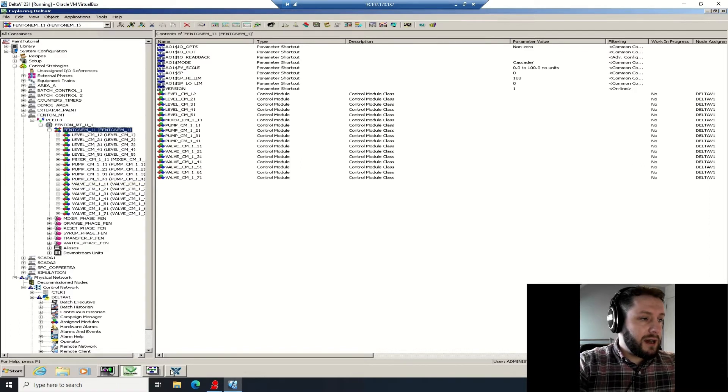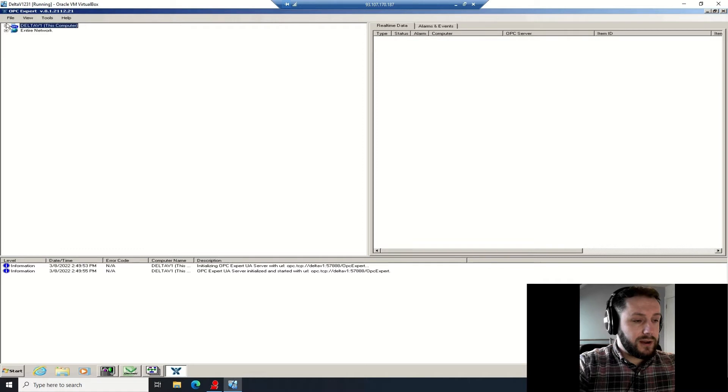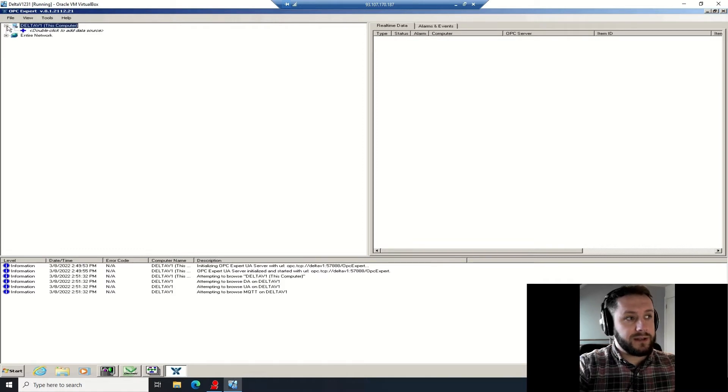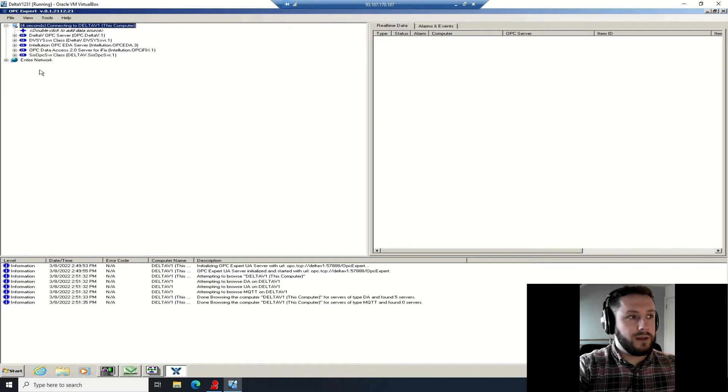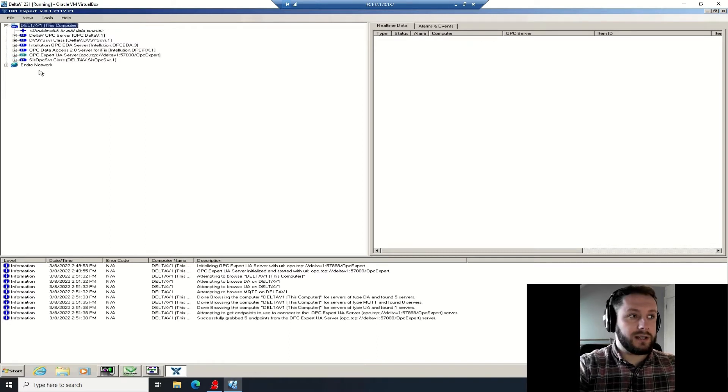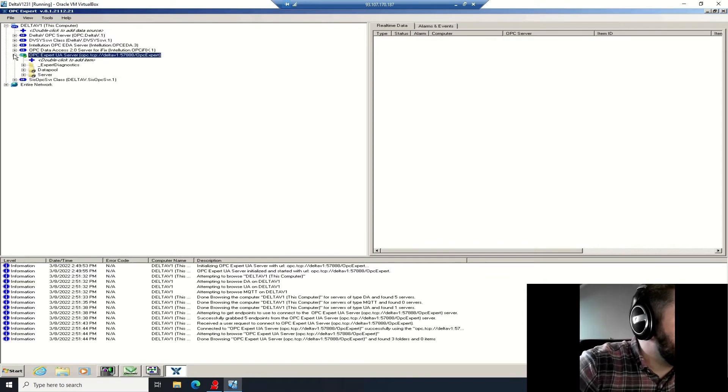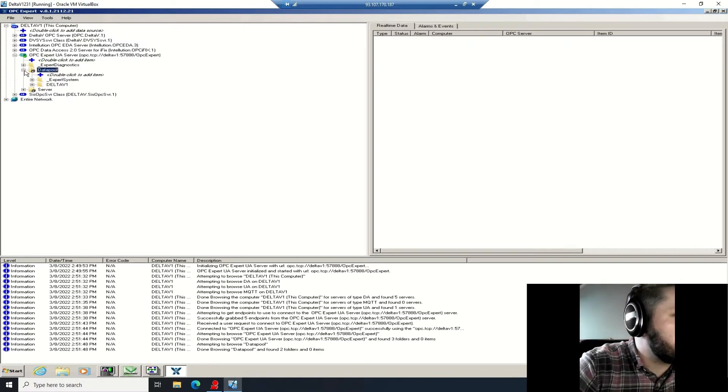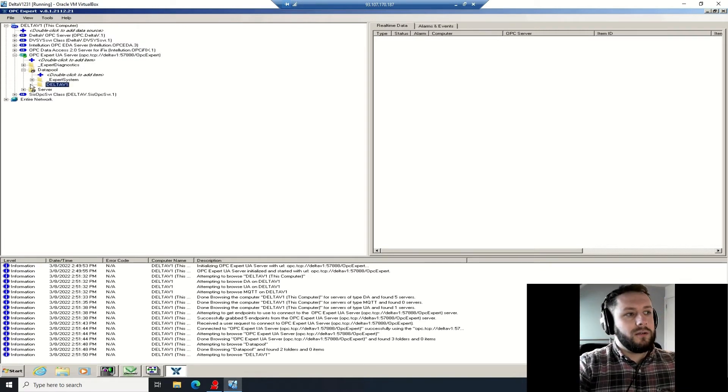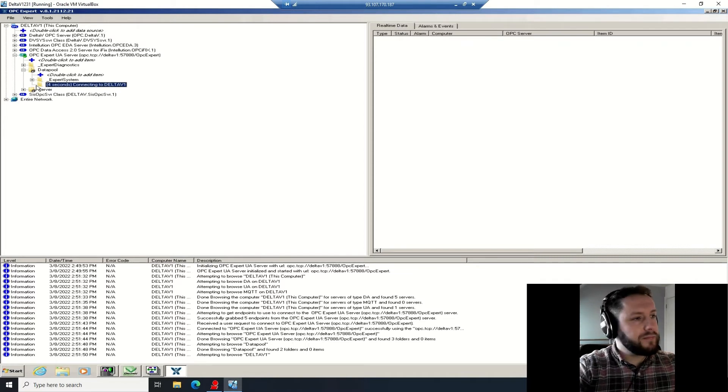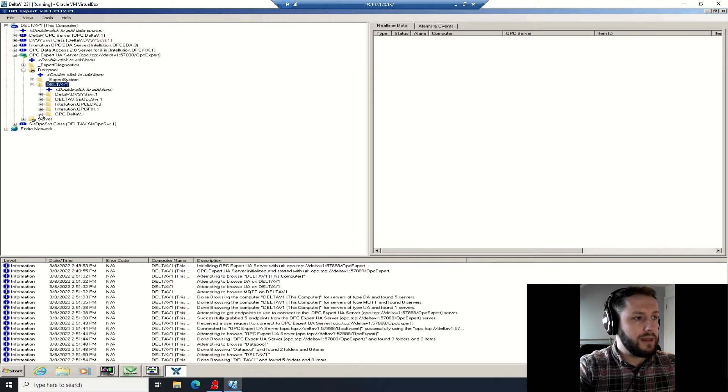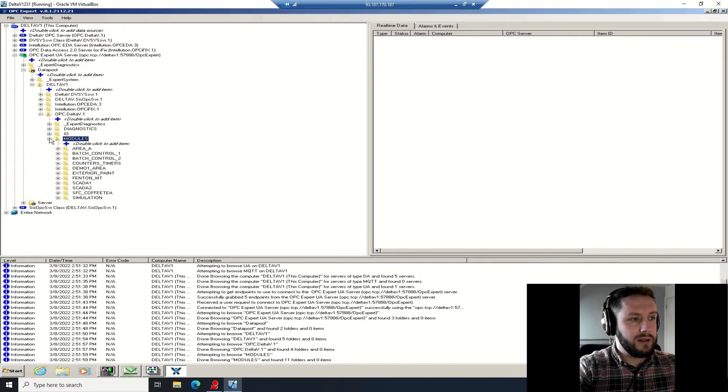By running software called OPC Expert, you run OPC Expert and this will create a communications tunnel. It uses only one port and it's an executable, so it doesn't affect any running services. You can see here OPC Expert UA Server, and then you see OPC TCP, and you have an address there of the server. We're going to need to remember that address when we're creating our communications channel, and then I'm showing you here how I branch down.